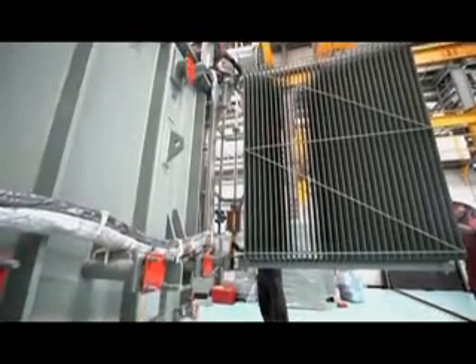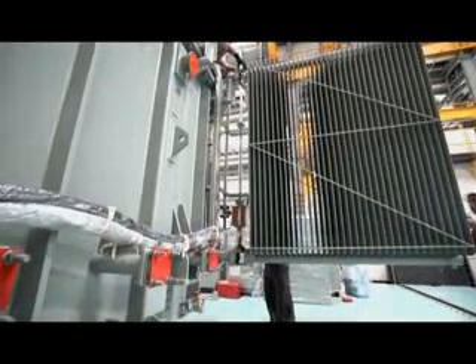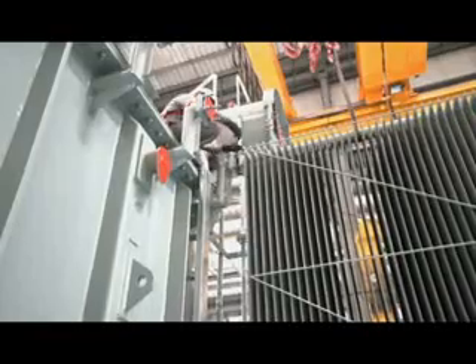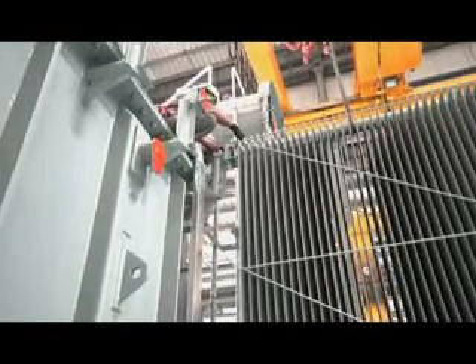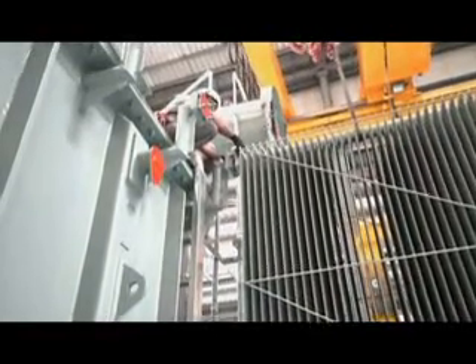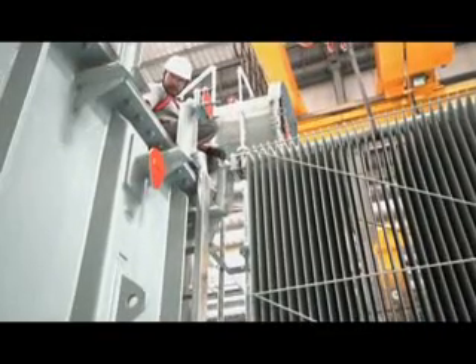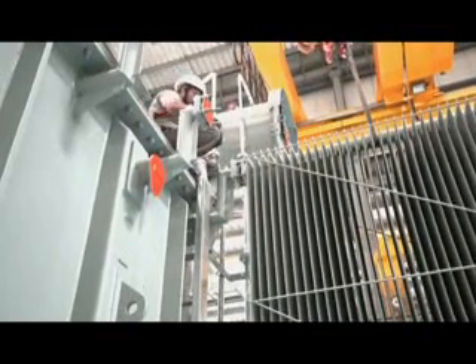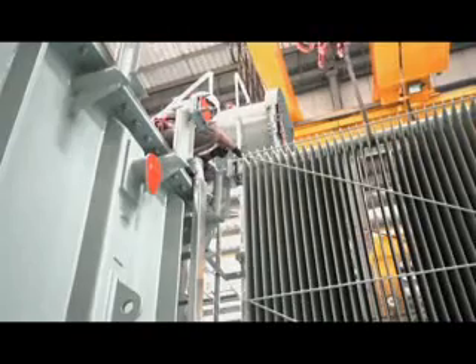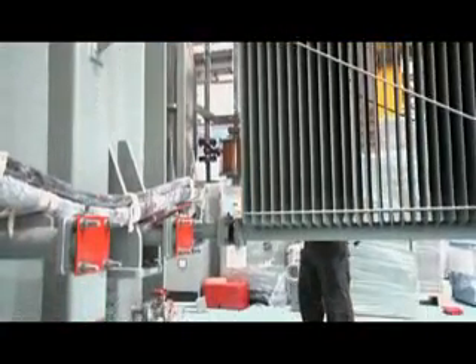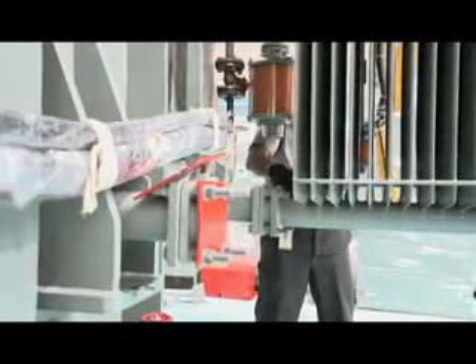Under loaded condition, warm oil increases in volume and comes to the upper portion of the main tank. Then this oil enters the radiator through the top valve and cools down by dissipating heat through the thin radiator walls. This cold oil comes back to the main tank through the bottom radiator valve. The cycle is repeated continuously till the load is connected to the transformer.